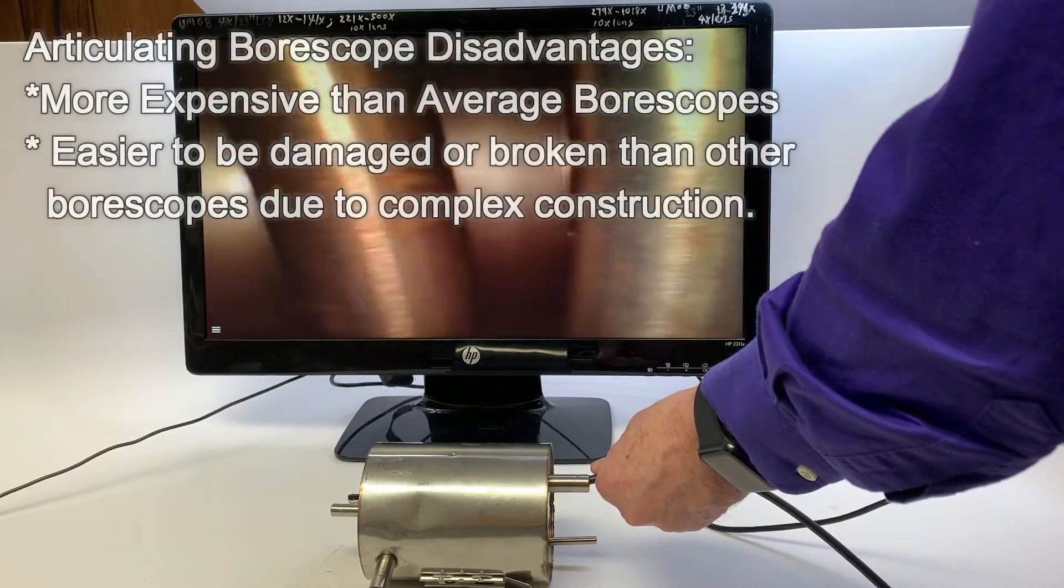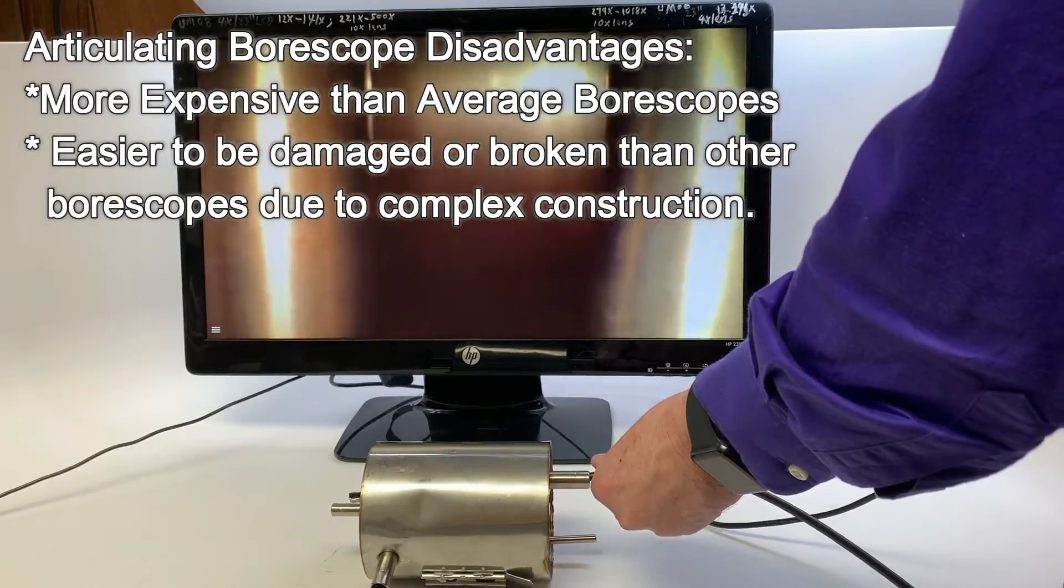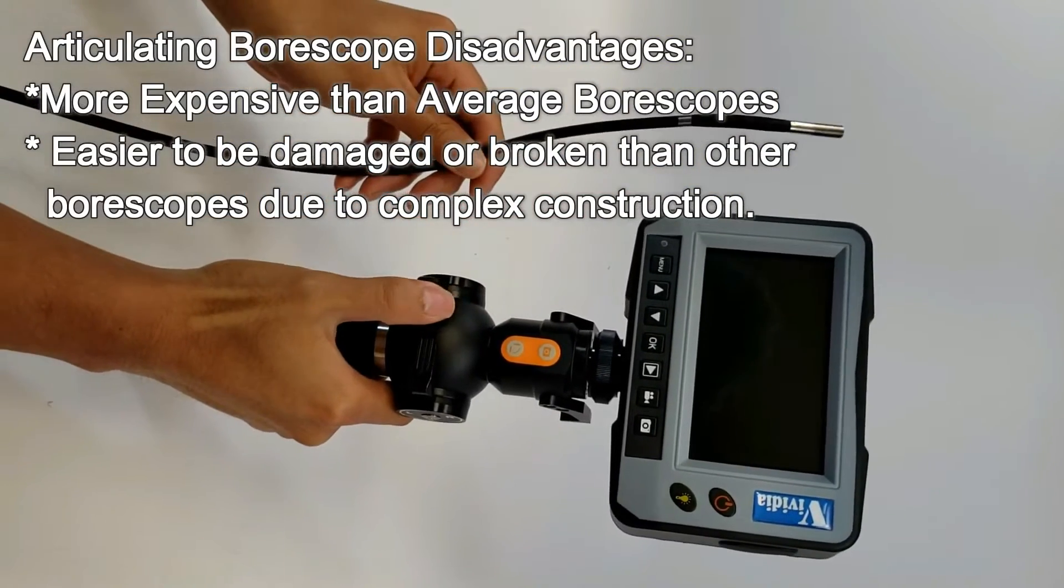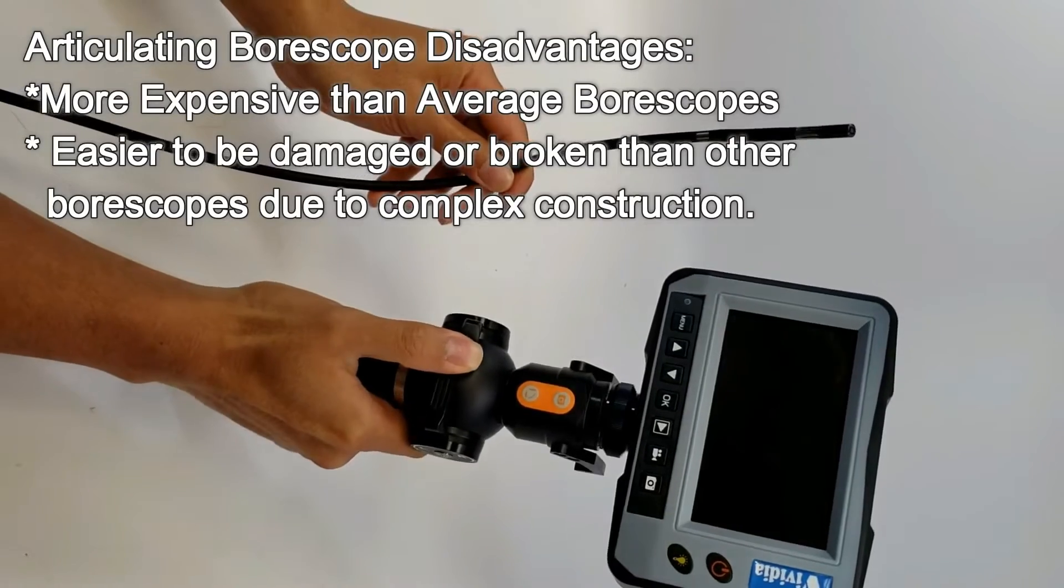Some of the disadvantages of articulating boroscopes is that they normally cost more than other types of boroscopes due to their more complex construction, and they are more susceptible to damage due to the force needed for articulation.